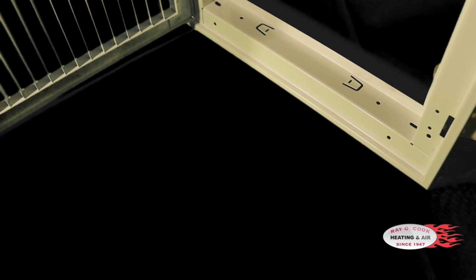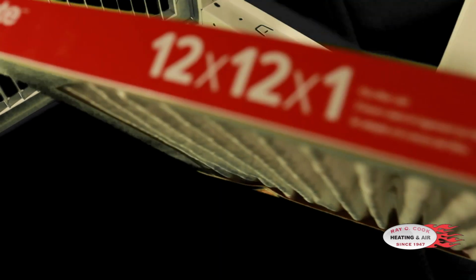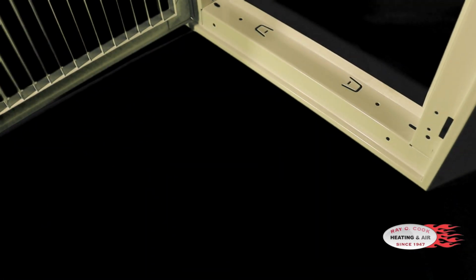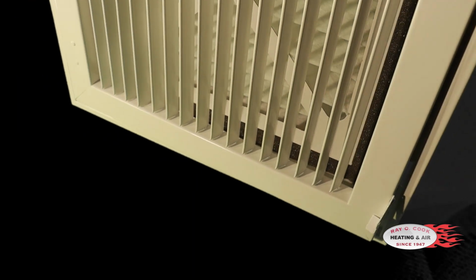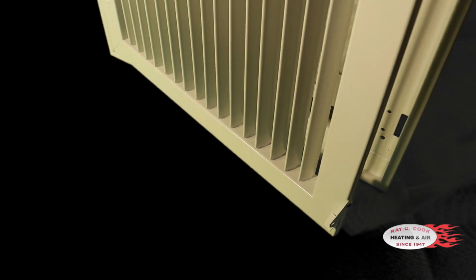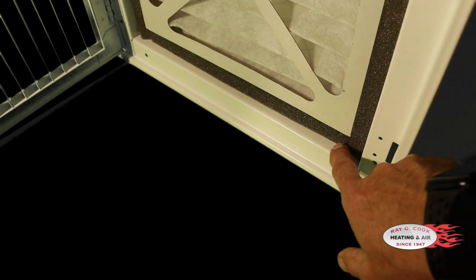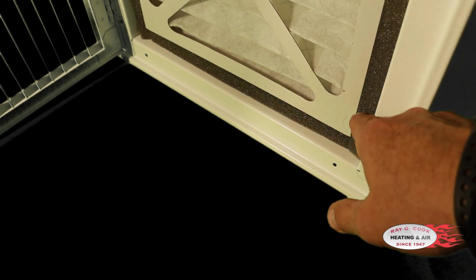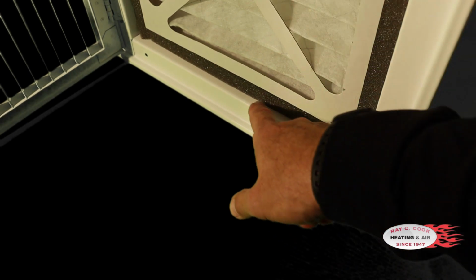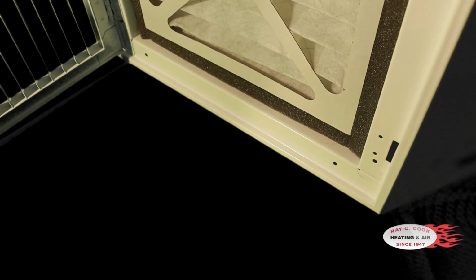So we talked about some options to improve the air quality by going with more surface area. Instead of a 1-inch filter, going with a 3-inch filter. So let's take a look at what that can do for you. Okay, so now we have a 3-inch filter that gives us a lot more surface area and less resistance. When we look into that application, you can see that this particular manufacturer has this gray foam all the way around, so it pretty much seals up any bypass that's going to be in the filter grill here.